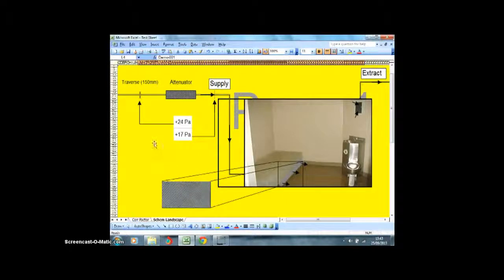So I came up with the idea to traverse 1 and 2 points and relate that to a pressure just before the ductwork went into each cell. Each cell had an identical layout, so I would assume, well, they say never to assume, but I would imply that the pressure profile for each cell was exactly the same. So as long as I can prove a volume at the traverse point and then tie that into the static pressure taken at this test point, that would tell me exactly how much air I'd have at this point, so that I could obtain a balance.